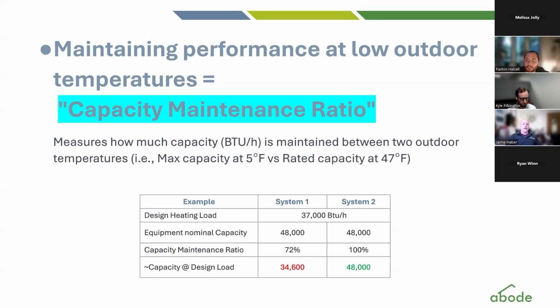So when I look at different proposals from folks, I look at this capacity maintenance ratio very carefully, especially if the heat pump is going to be their sole source of heat. If you're replacing an oil system or a propane system, we want to look at that capacity at 5 degrees and ask, is it really going to suffice?